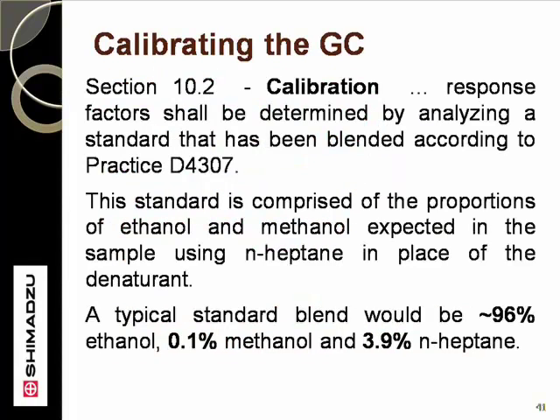The commonly used ASTM D5501 method has specific instructions that mass relative response factors, MRRFs, should be determined by analyzing a prescribed sample made of ethanol approximately 96%, methanol 0.1%, and heptane 3.9%, all in mass percentages. In this case, heptane is a substitute for the denaturant in the sample. The MRRF values are calculated from the ratio of the ethanol and methanol response factors to that for heptane.